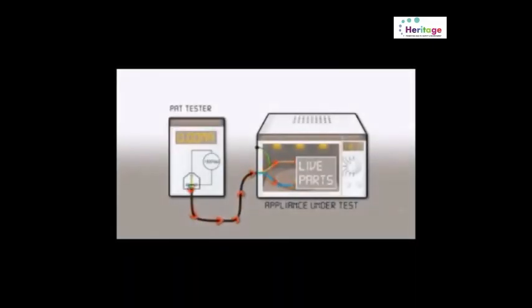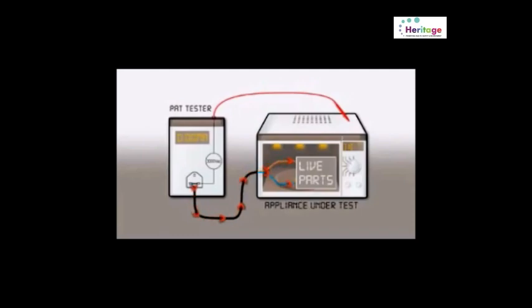The flash or dielectric strength test is carried out by applying a high voltage, typically 1500 volts AC, to both the live conductors of the appliance. If there is any breakdown in the insulation, the PAT will measure the current flowing through the insulation to protective earth. A test probe is required when testing a Class 2 appliance. The probe is applied to any exposed metal parts. If there is any breakdown in the insulation, the PAT will measure the current returning via the test probe.